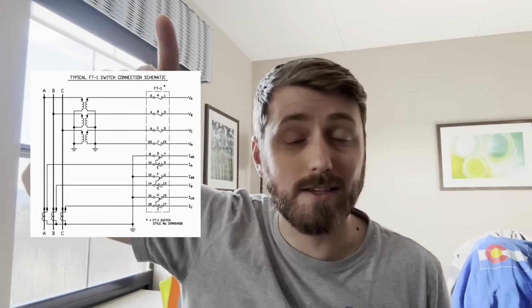The bottom is always connected to the source and the top always goes to the relay, because that's how the test switch paddle works. Why have a test switch that isn't designed to work with a paddle?